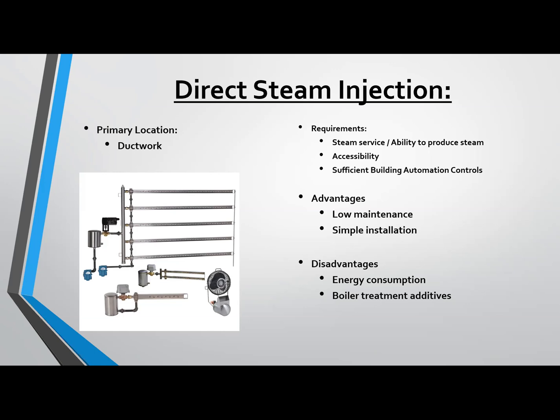A couple disadvantages to direct steam injection: energy consumption. You are producing steam, so you have boilers, chillers, condensate pumps, returns, and drains. You've got all kinds of stuff that's sucking energy, so it is a bit more energy consumption and energy cost-wise.